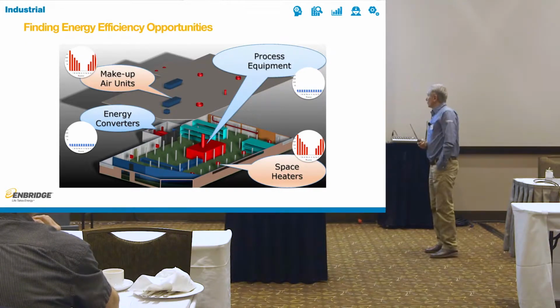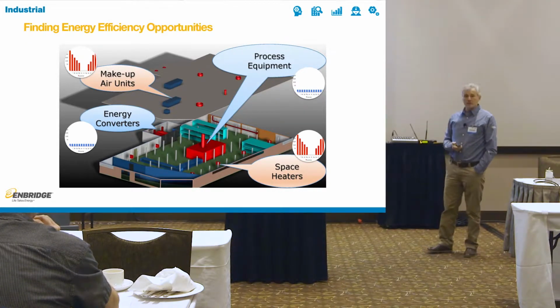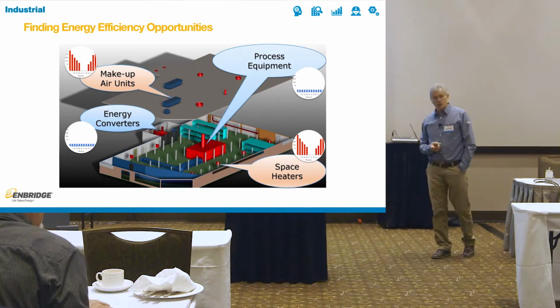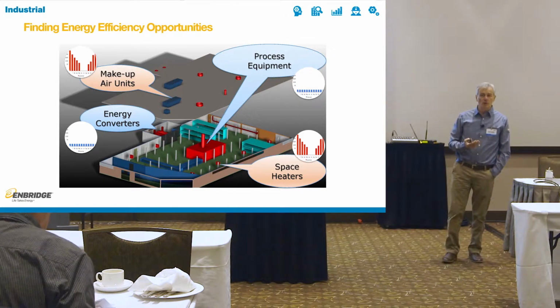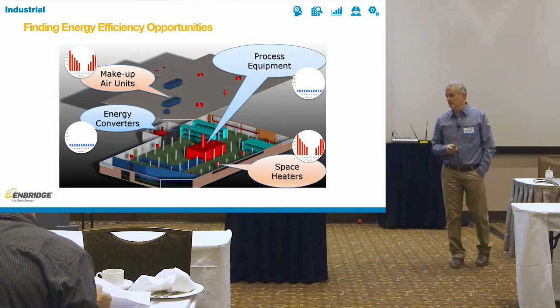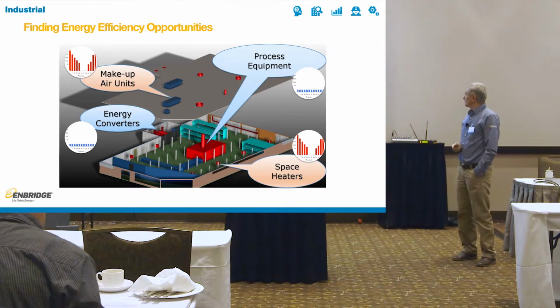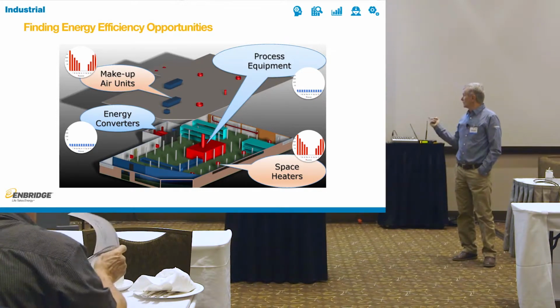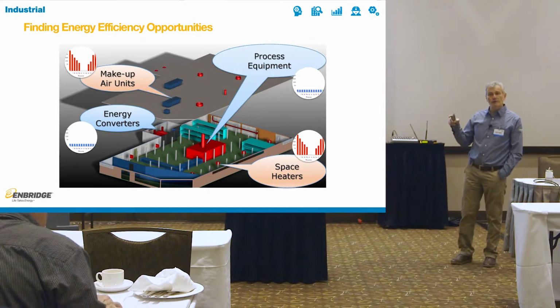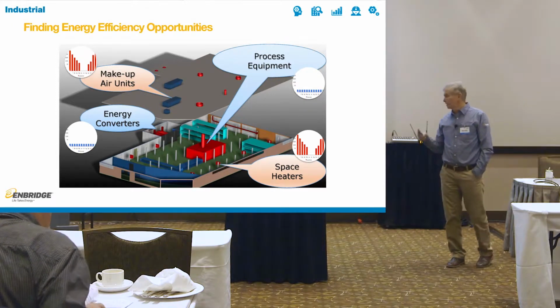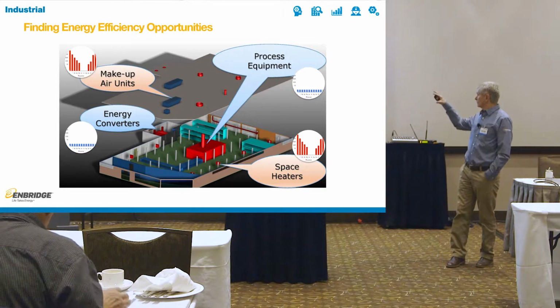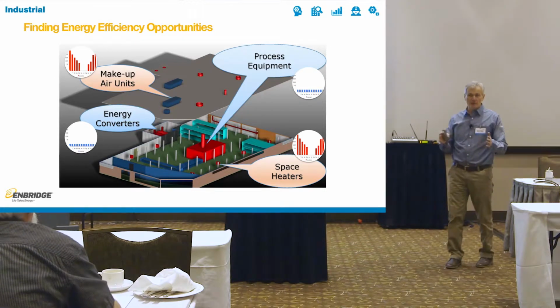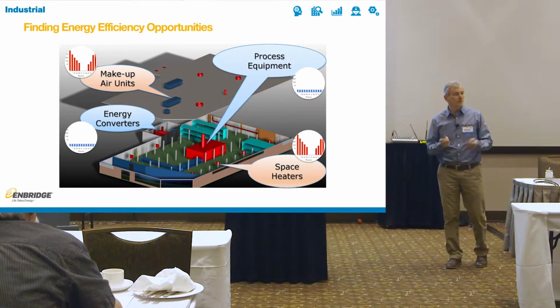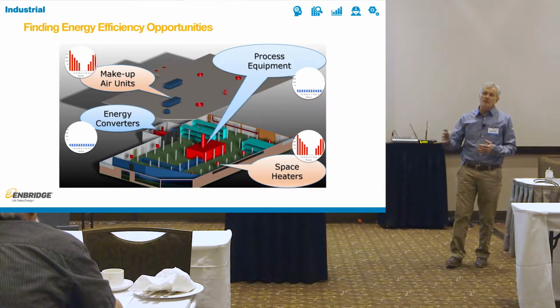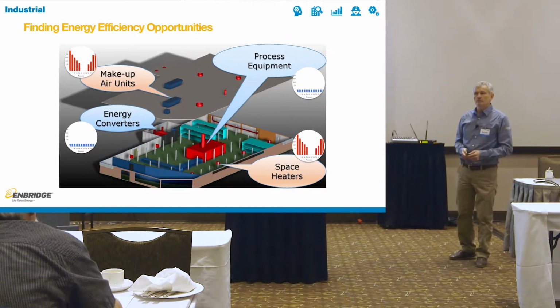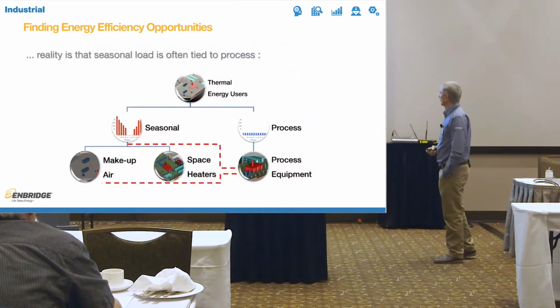So where do we look? Process equipment, obviously, falls under the process load. Energy converters fall under the process load, your boilers, and on the electricity side, your compressors. On the other side, you have makeup air units and space heaters. Those are the ones that fall under the seasonal load. So on first blush, when you look at makeup air units and space heaters, all of us understand it. Seasonal load, everybody immediately says, oh, that's a space heating load. That's for heating the space.